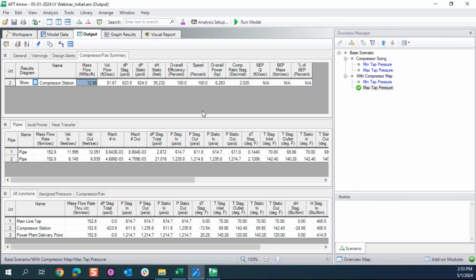So looking at this, what we set out to do was size a compressor for this compressor station that it could meet those 1,200 pressure demands while giving a large amount of mass flow. And it does seem like this curve is giving results that would be good for this system.